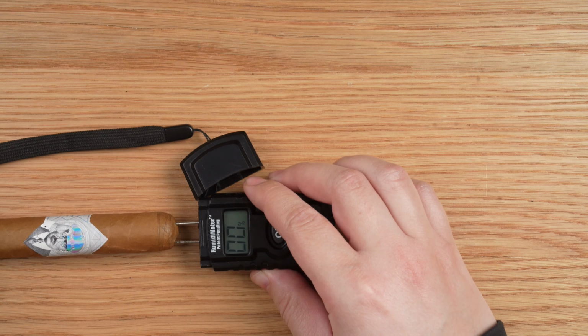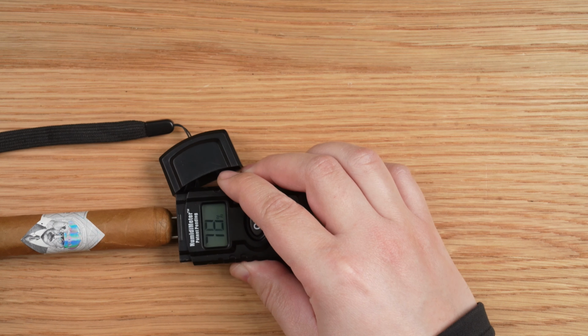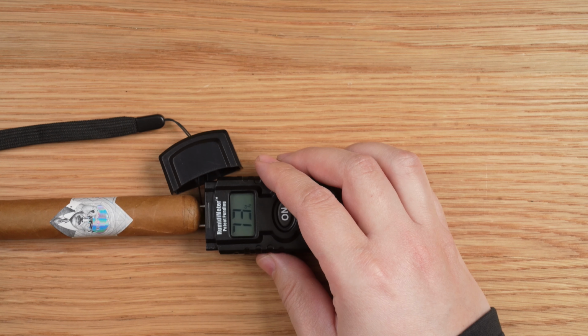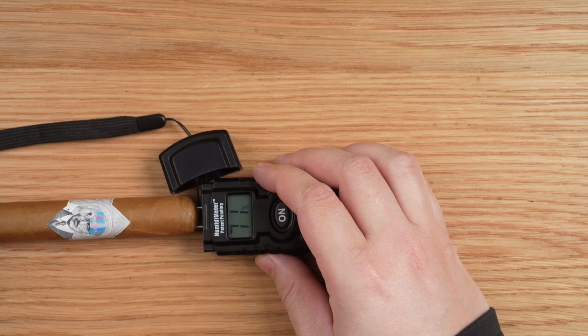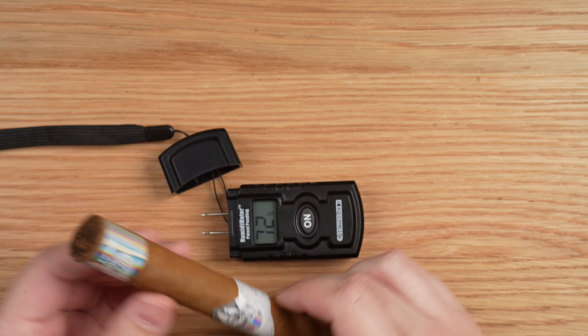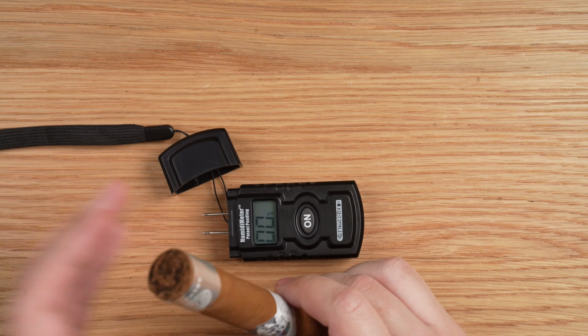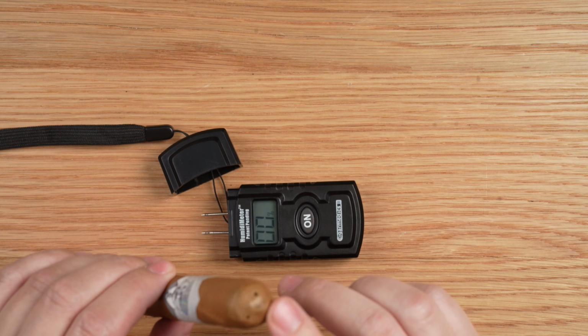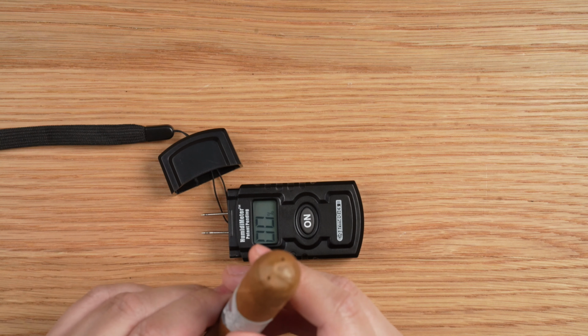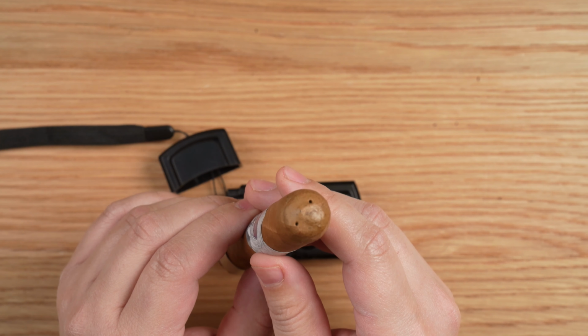This is going to puncture the cap, so it's going to leave a mark. The other thing it's also likely going to do is produce slightly higher results than the foot, and that's just some simple physics here: the foot is open, so air can go in and out, whereas the cap is closed, so the moisture gets trapped. Now you can see there are two small holes in the cap.